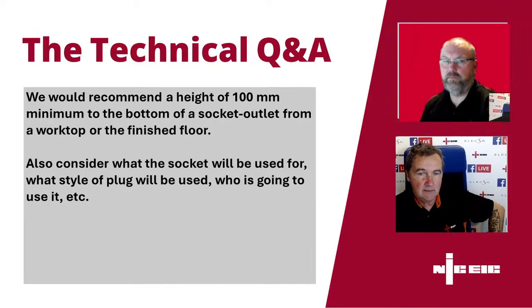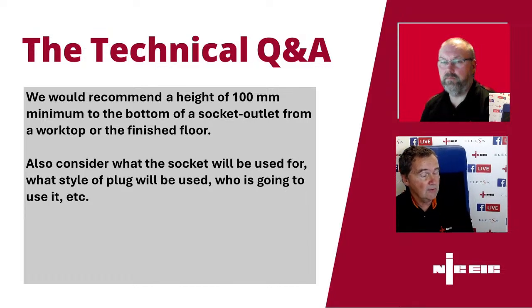I guess the thing I'd comment on there is that ultimately the earthing arrangement is provided by the DNO in this instance, because they're saying it's got a combined protective and neutral conductor, but it's allowing us to create a PNB earthing arrangement which doesn't have the same slightly onerous requirements as PME does. So although it's connected with the DNO, I wouldn't suggest it's an issue of the DNO. Historically, we started off with TT, then went to TNS when they provided us with an earth, and then they realised they could go from three conductors to two and give us a combined neutral and earth. So it's something we know is around, but it's just a different form of TNCS, not PME, and it might give us some advantages over PME in those installations.